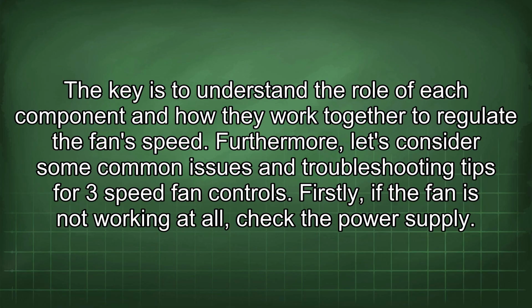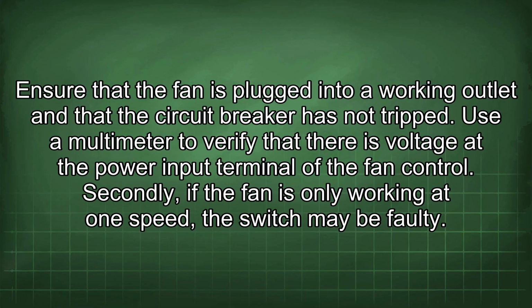Firstly, if the fan is not working at all, check the power supply. Ensure that the fan is plugged into a working outlet and that the circuit breaker has not tripped. Use a multimeter to verify that there is voltage at the power input terminal of the fan control.